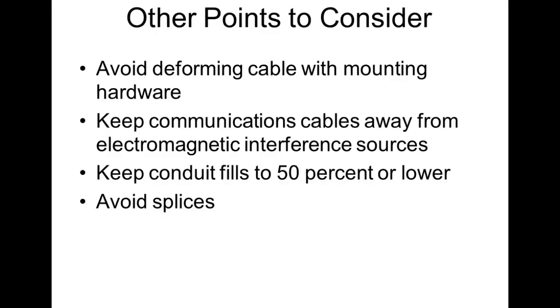Keep conduit fills to 50% or lower. This is in the National Electrical Code. I've been in conduit where they have cables crammed tight as they can get them in there. All those cables are trying to emit electromagnetic interference and trying to receive electromagnetic interference, and now you've got them all crammed in a conduit so they can't dissipate heat. So when dealing with commercial wiring and conduit, one thing you have to calculate is the fill: how many different gauge conductors you can put into a conduit without filling it over 50%.